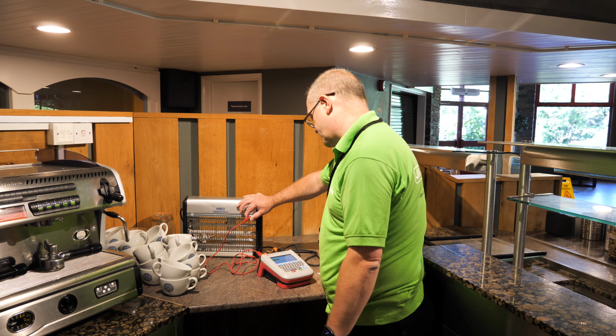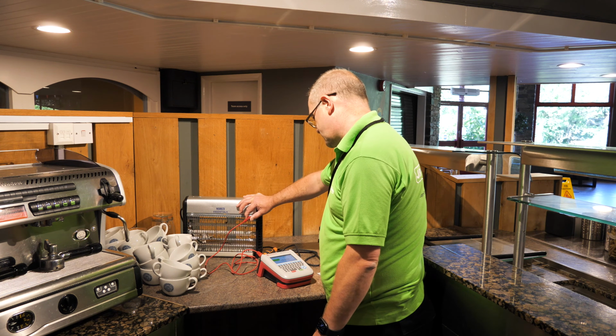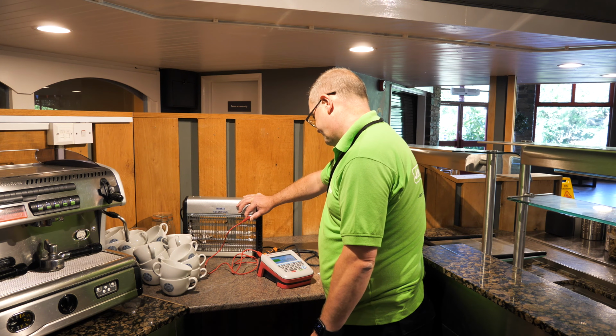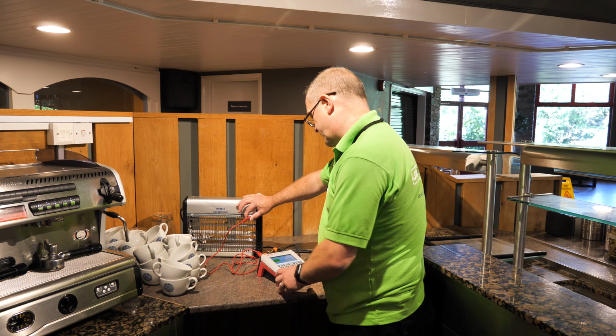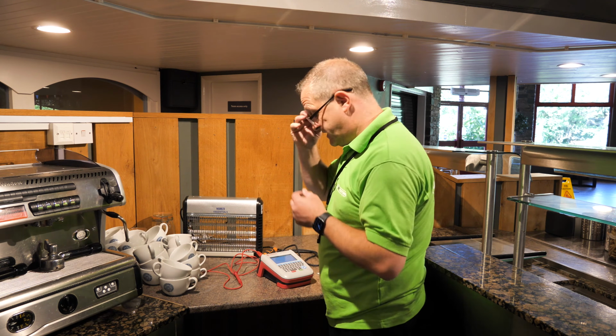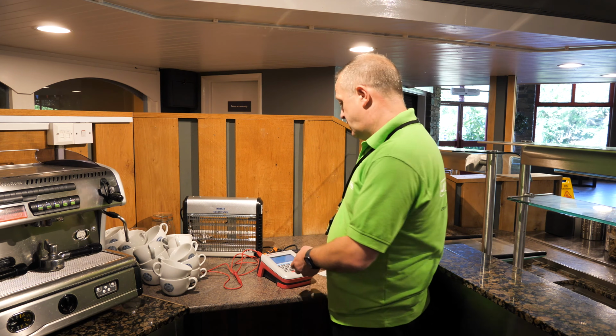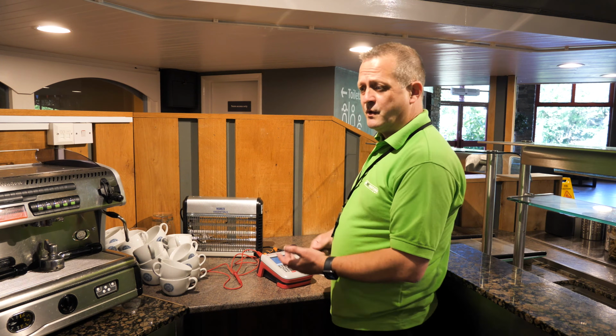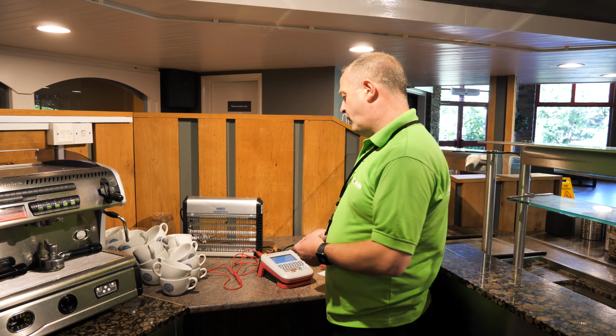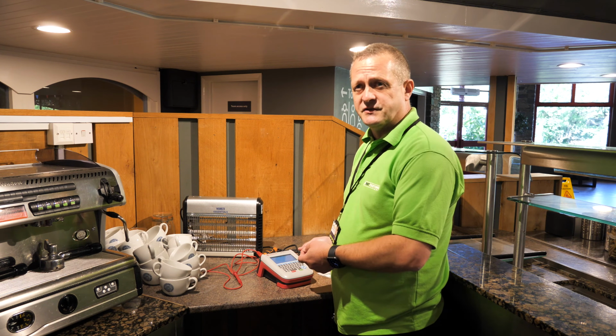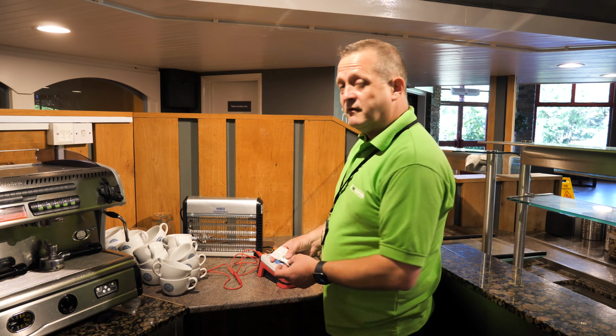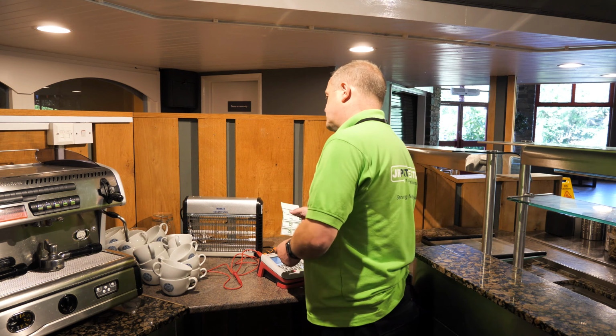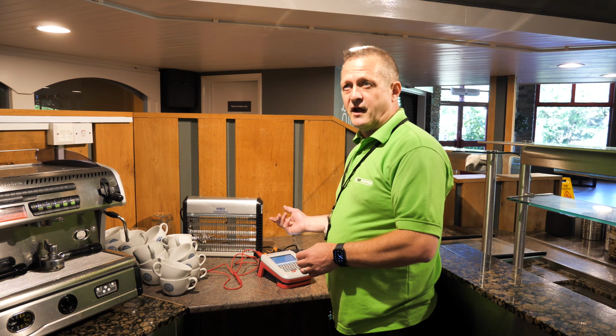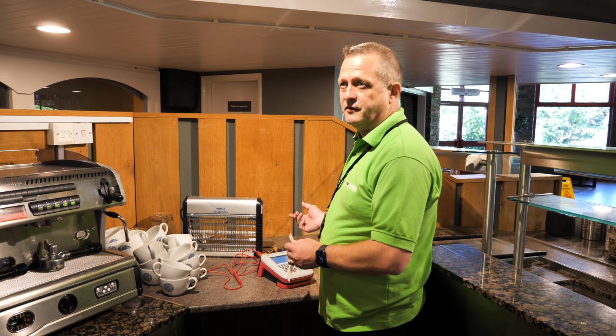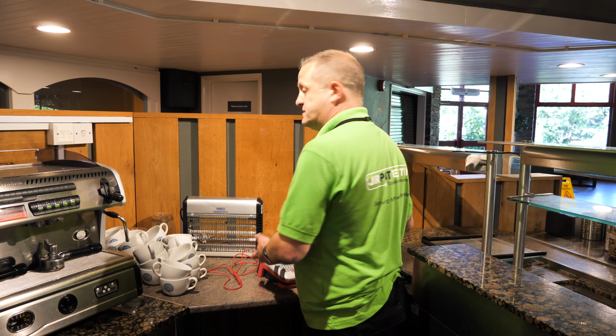And then we'll go into the first part, which is the earth continuity test, and then it's straight into the insulation test, and both are showing a pass. So I'd record all the details into the PAT testing machine, or depending on which device you use, whether you write that down on paper or record it onto a laptop to send to the office. We will then fill in the label and apply that to the appliance, ensuring that we've removed any old labels from the appliance, and that appliance has passed.